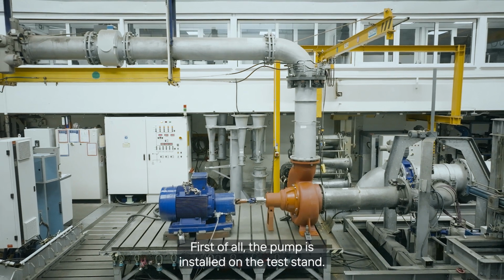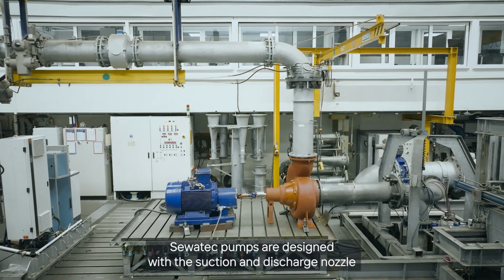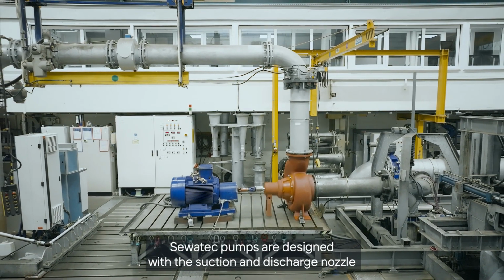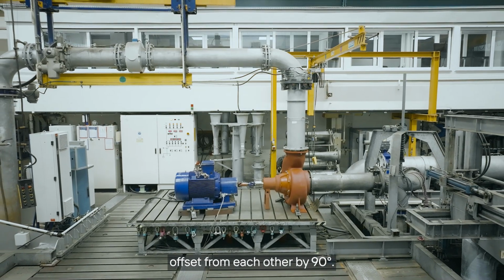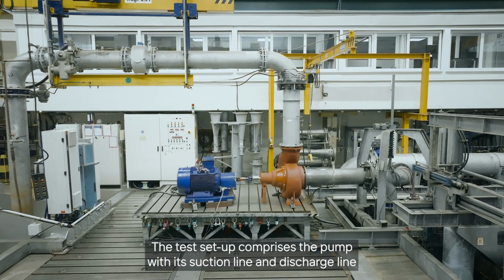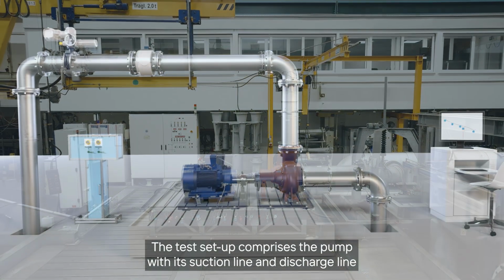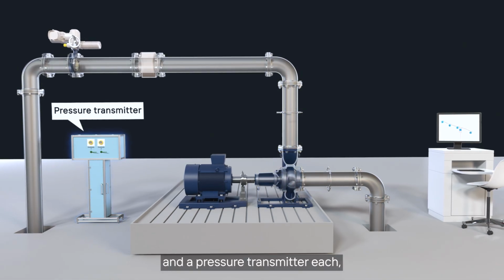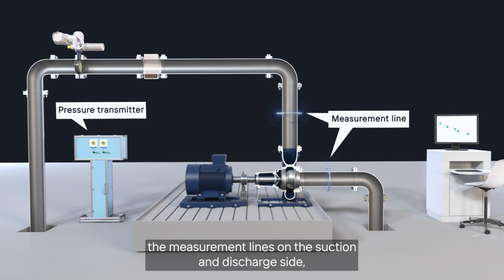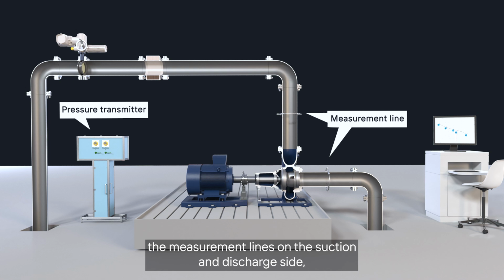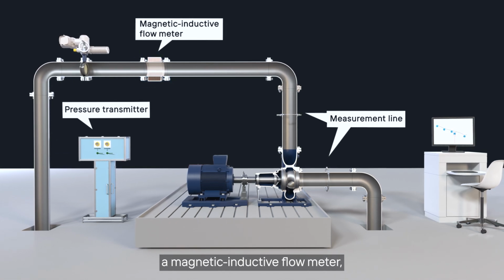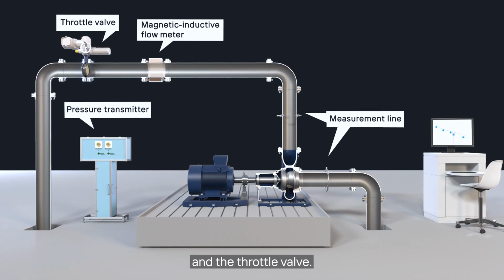First of all, the pump is installed on the test stand. Sewatec pumps are designed with the suction and discharge nozzle offset from each other by 90 degrees. The test setup comprises the pump with its suction line and discharge line and a pressure transmitter each, with the measurement lines on the suction and discharge side, a magnetic inductive flow meter and the throttle valve.